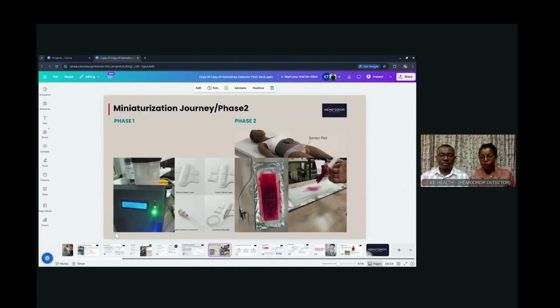Okay. So first, we mentioned the challenge of clots because in our first phase, we were suctioning blood from the pad, so a lot of clots would be retained in the pad. But moving to this next phase, we have addressed that because here we are using a capacitive method of sensing. That means anything wet, say the blood being so heavy, will be accommodated because when the blood is on the pad, it's still wet, and this mechanism is more like an electrical field that goes right above it. So it doesn't make contact with the pad, but when the pad is on top of the sensor and the field, that means it's within the electrical fringing field. So any blood or anything wet that comes in contact will be accommodated for. The ions of the blood or the ions of the clots are going to show up.